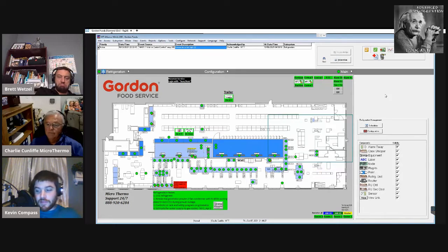That's awesome. Now the one thing that Kev and I discussed when it comes to racks - it's not a limitation, it's a rule we put onto ourselves, especially with CO2. There are certain inputs for oil, temperature, and pressure that we want to be absolutely instantaneous. This is just the way the engineers want it.